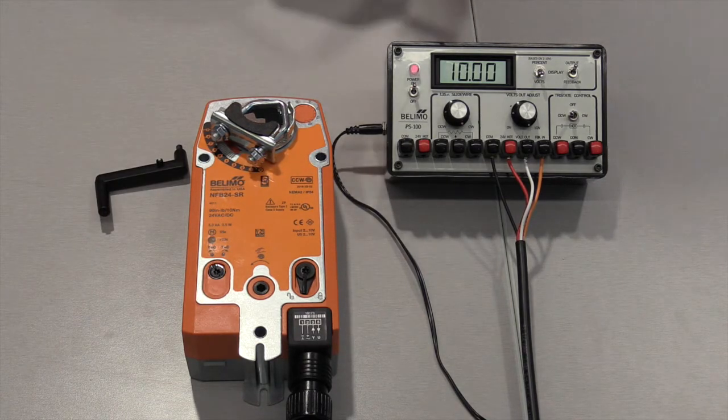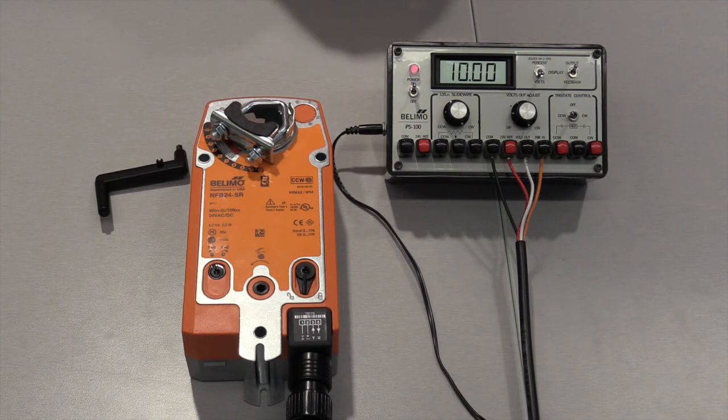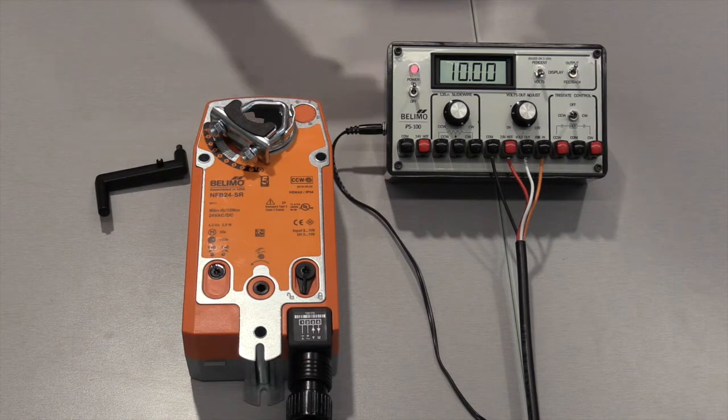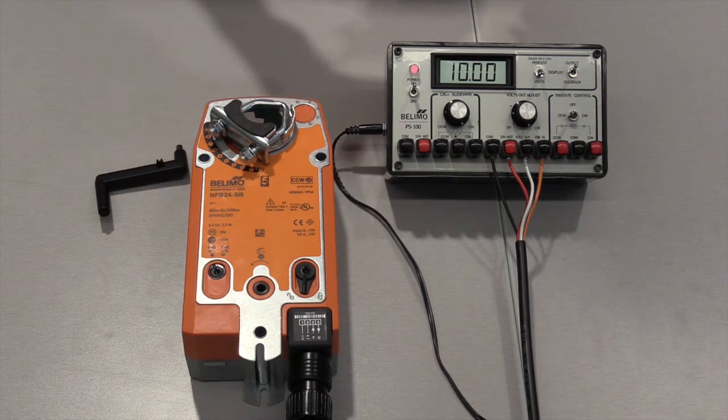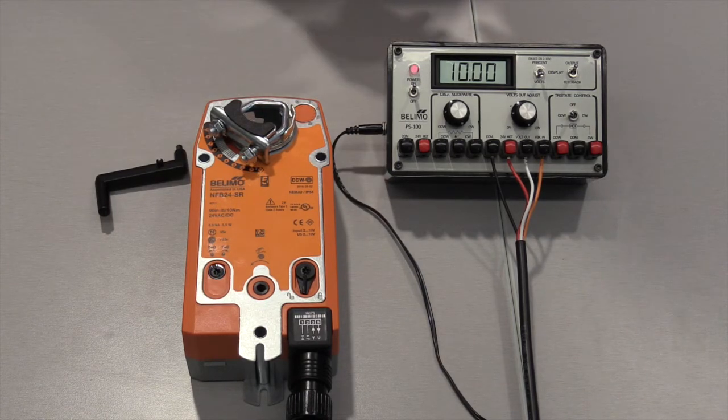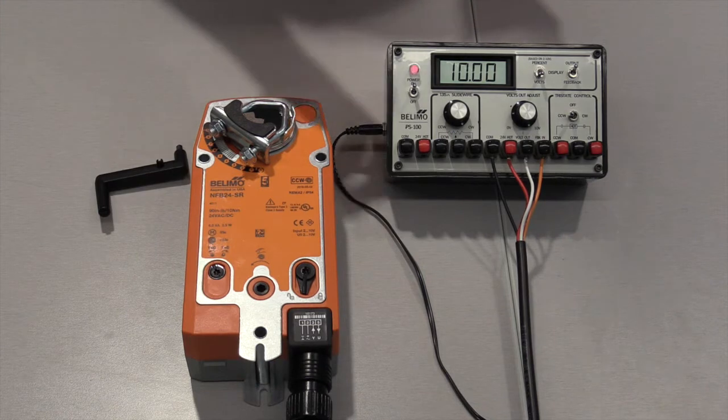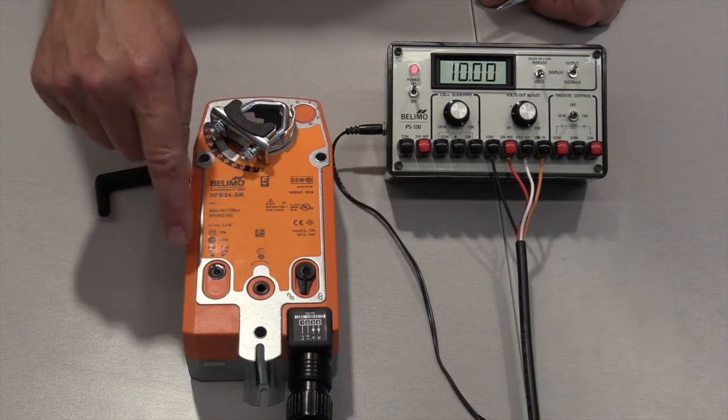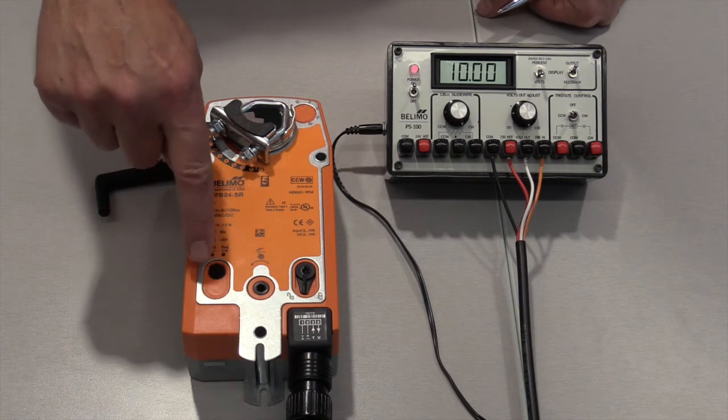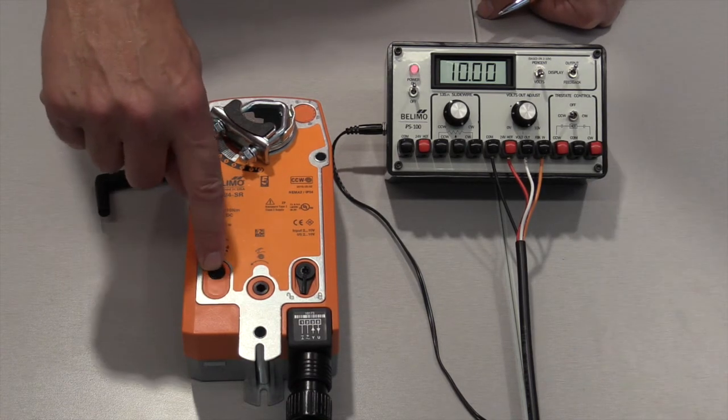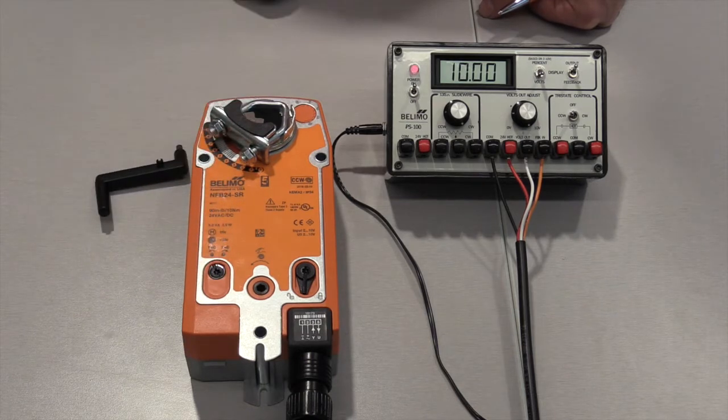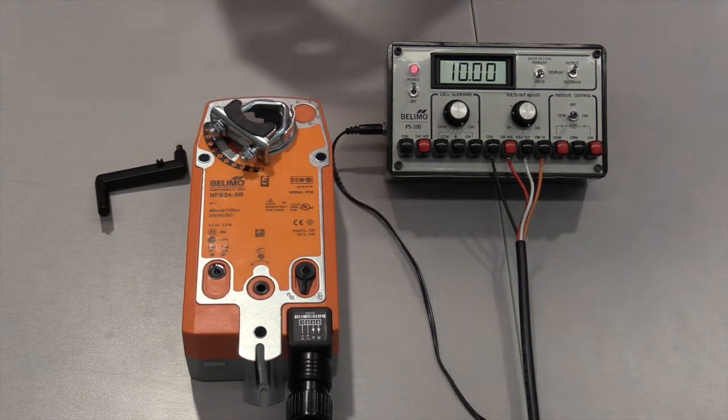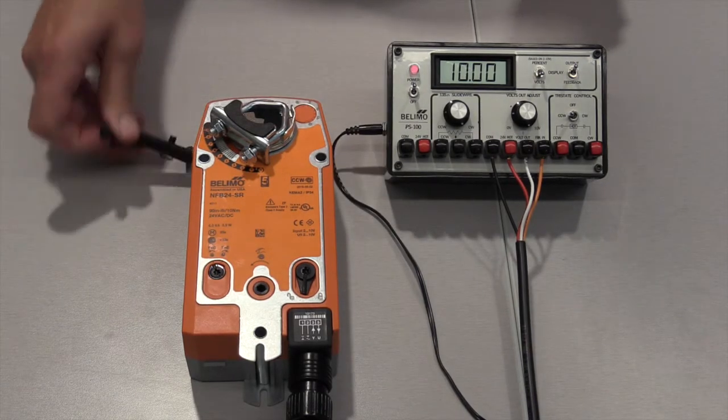It has happened in Belimo tech support, we'll get a phone call from a customer and they'll say that my actuator is behaving in the opposite direction. It's turning in the opposite direction than what I want, and what they're saying is on a 10 volt signal the actuator closes, on a two volt signal it opens. We'll direct them to this switch on the face of the actuator and they just need to change the rotation of this switch and it'll fix the problem. Now there are some building management systems that call for a reverse acting actuator and that's fine if that's what you need.